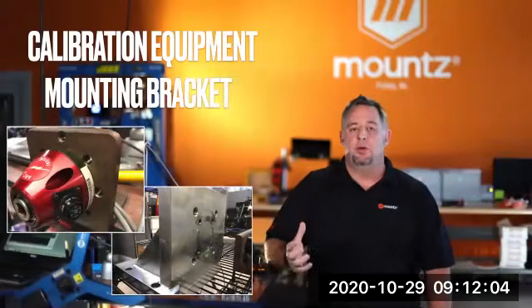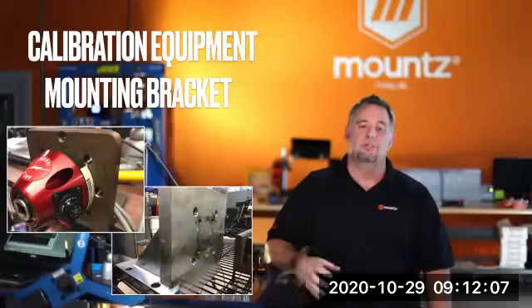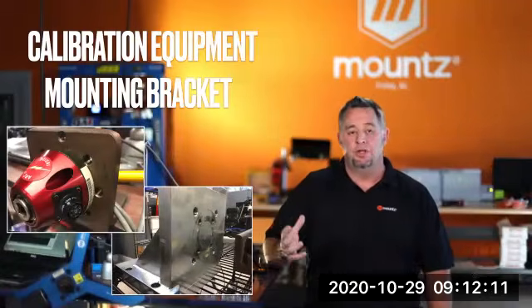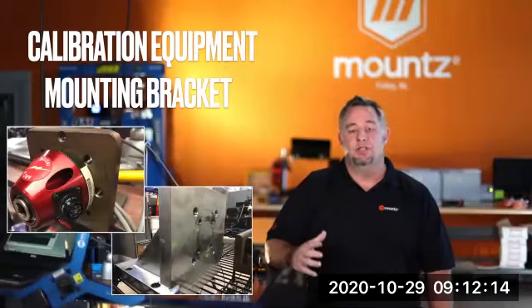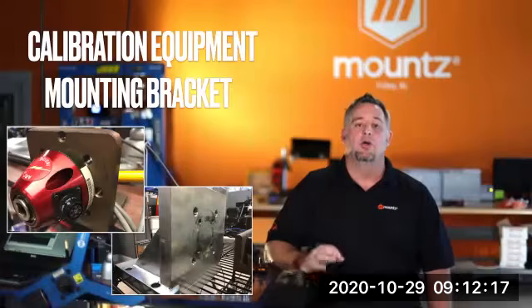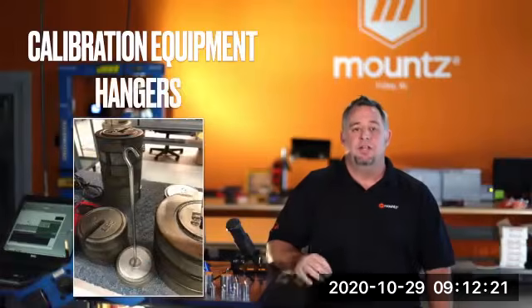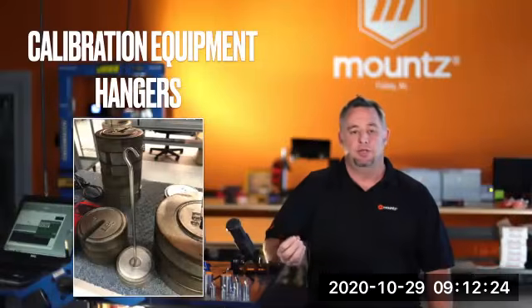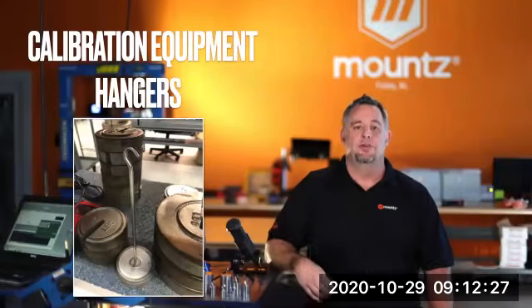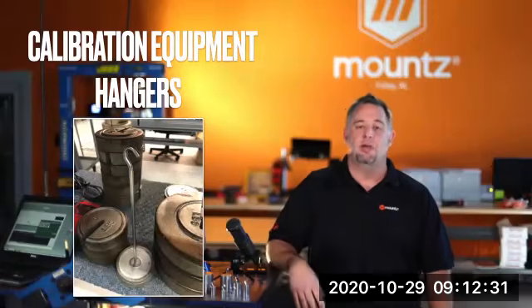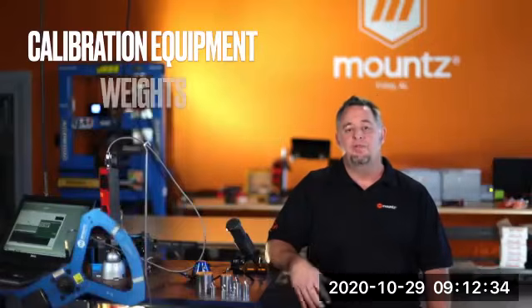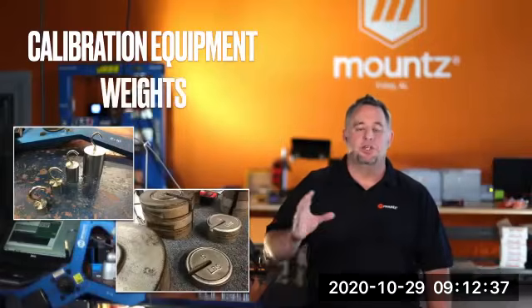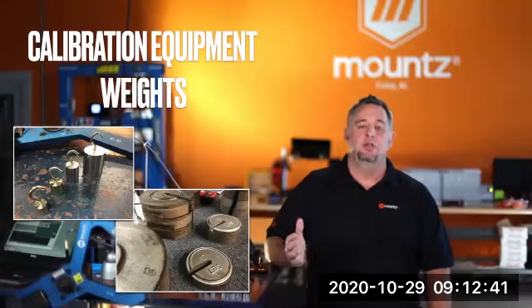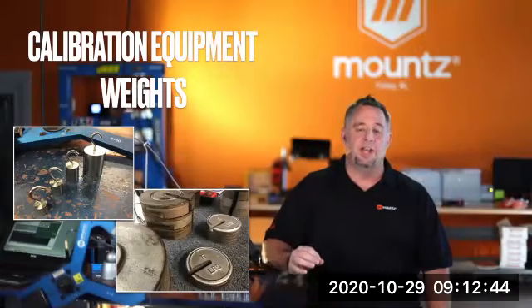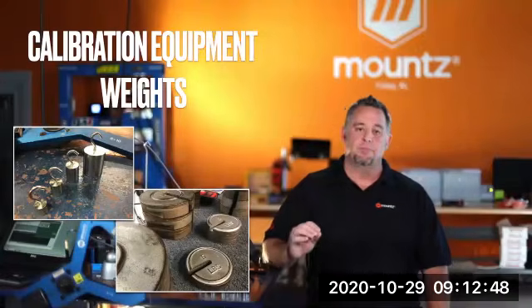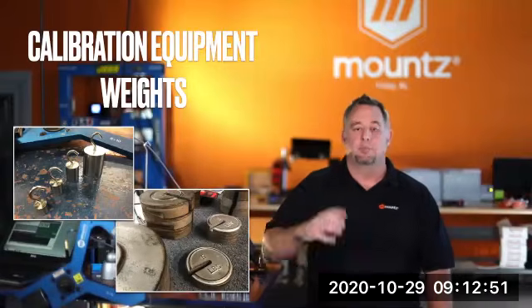And the other items that would be needed would be the mounting brackets, either mounting the analyzer or the transducer to a bracket to make sure that it is level. You'd also need hangers to be able to hang certain weights to replicate the values that you may need at a given known weight value. And then finally, the different weights. All of this equipment is sent out to another facility to be verified and or calibrated, everything except for the brackets for this particular calibration process.